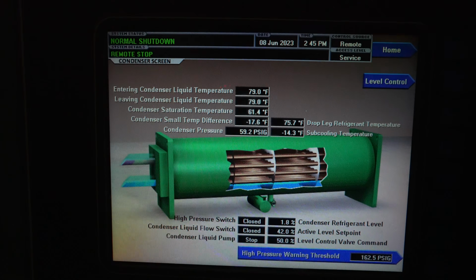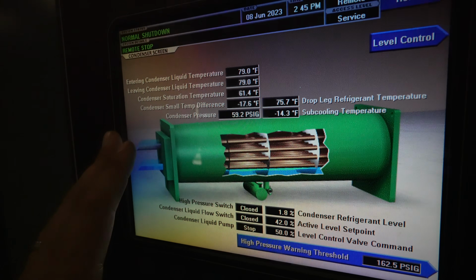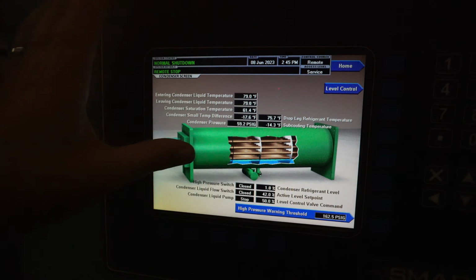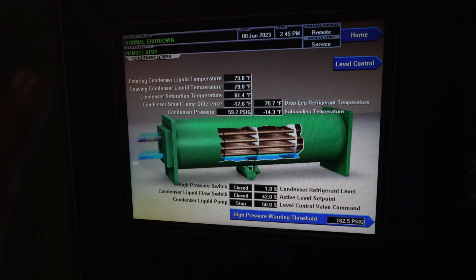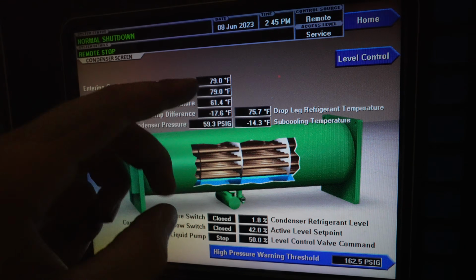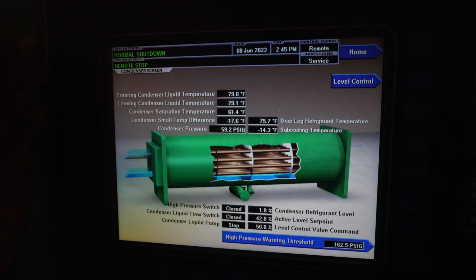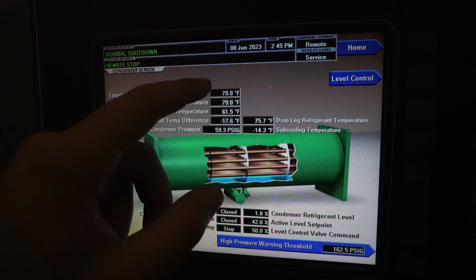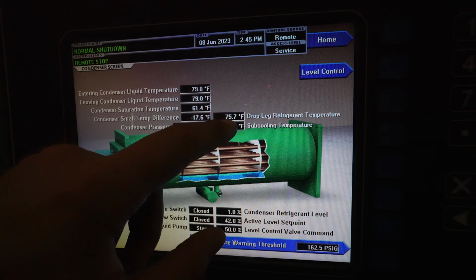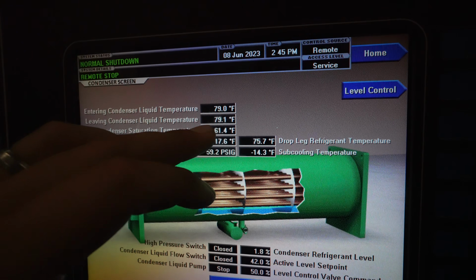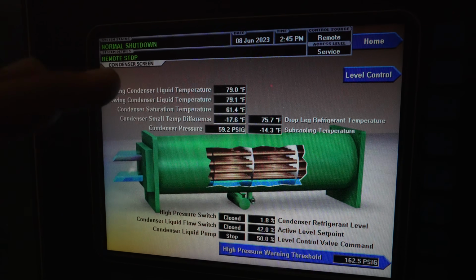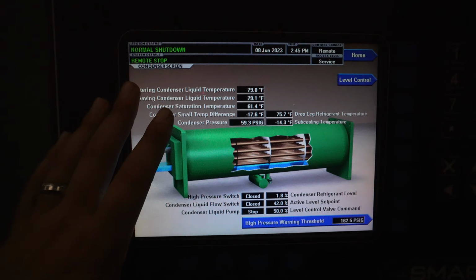So I brought in a second pump just to see what it would do on the header, because all these chillers are tied in on a central header. They're not a primary pump. And that immediately dropped me back down. I had about an 8-degree split. I came down into about 88 with about a 78, 79 coming into the machine. My subcooling came down to about 7. My saturation temperature came down and was floating right about that 89-degree mark, which I was very happy with. And that ultimately was the final resolve.